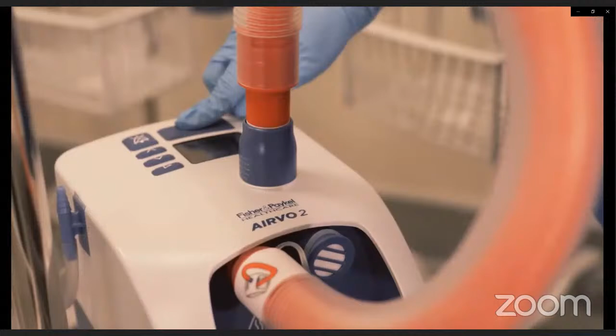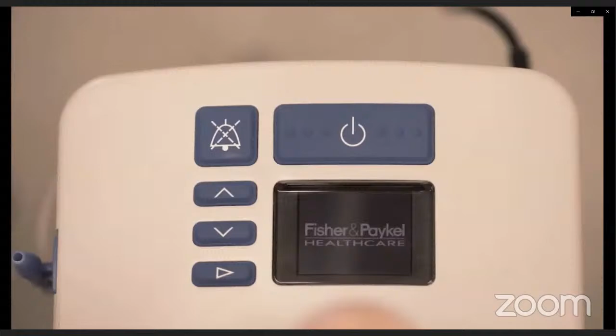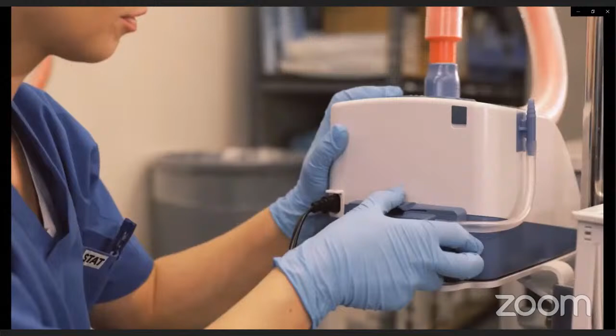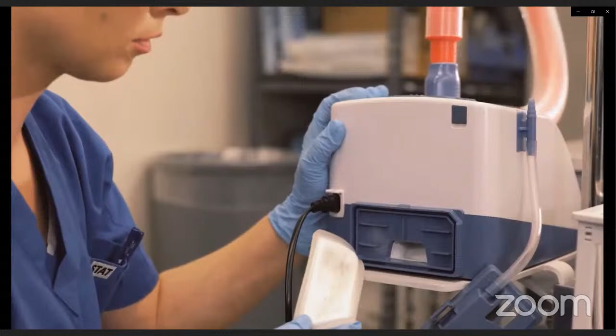Connect the power cable to the mains utility power socket and start the disinfection cycle by holding the on-off button for 3 seconds until the unit beeps. The AIRVO 2 will turn on and run a series of calibration checks, raising an alarm if any problems are detected. For example, you may be prompted to change the air filter. If so, remove the filter cover from the back of the AIRVO 2, discard the old filter and insert a new one. Make sure the filter cover is properly attached.